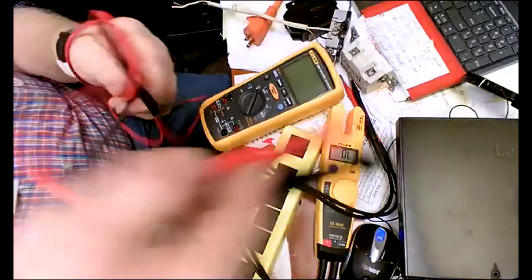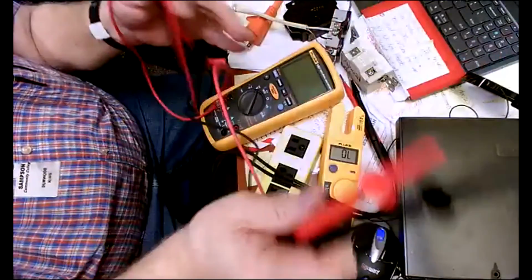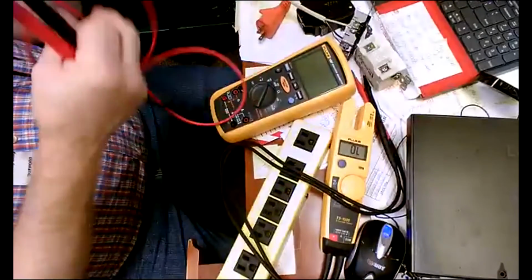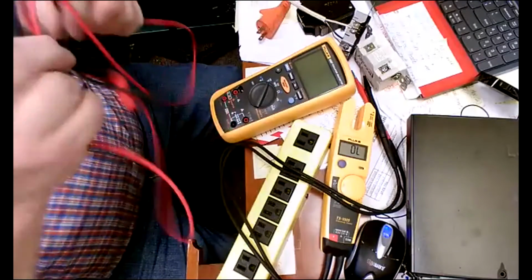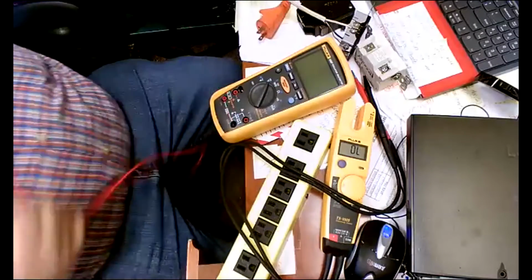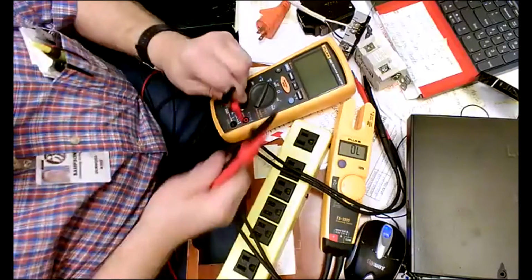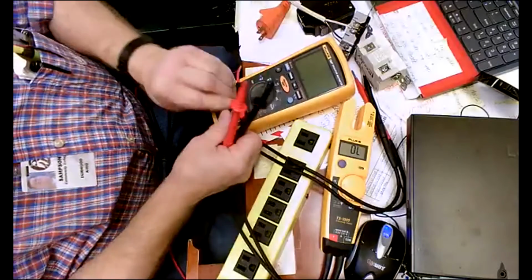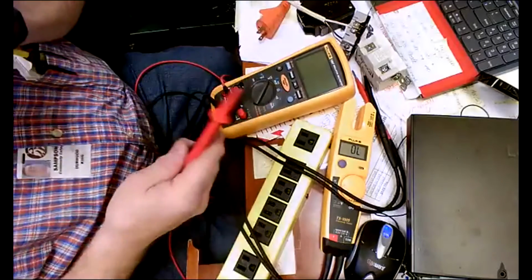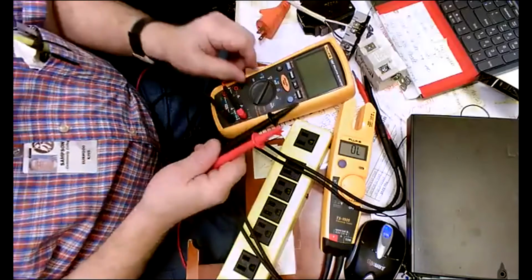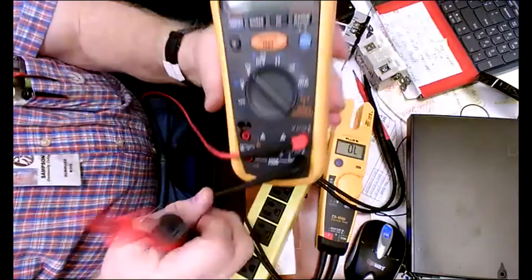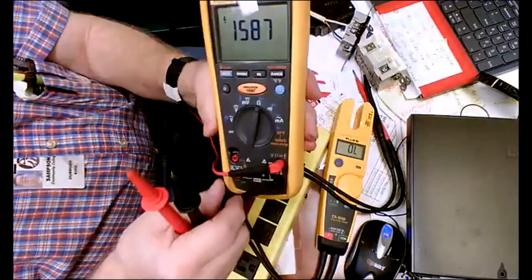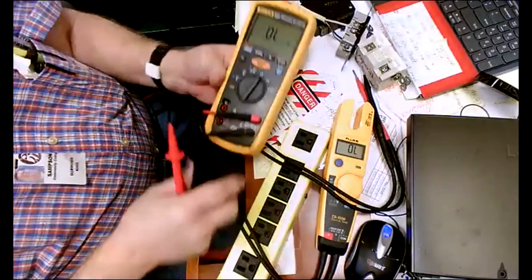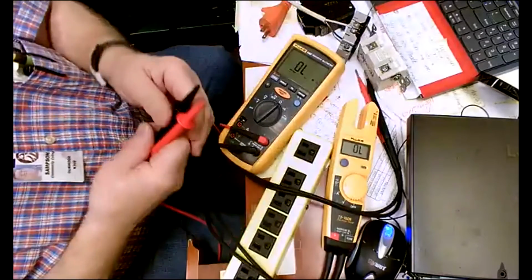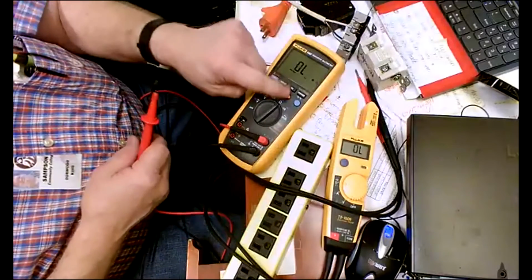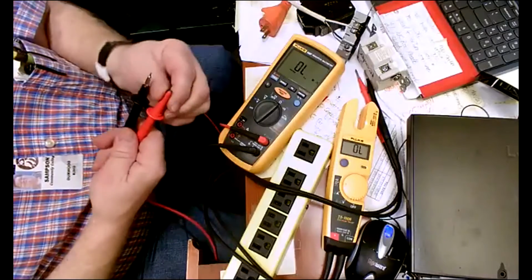So these are way more expensive leads right here. They've got quick connects on them, but they've got way less resistance in them. It's a more expensive meter, and you'll get into using this a little more later on, like for motor controls. So we're going to go with this meter here. It's got more features on it. You go to ohms there like that, and you can even do insulation tests on that one, on motor leads, all that stuff.